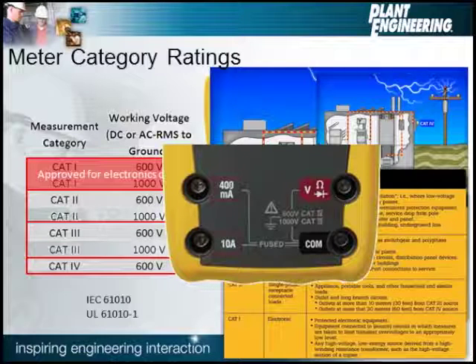Our Cat 2 meters are used for branch circuits, long branch circuits, and low incident energy exposures. Cat 3 is for service entrance, distribution panels, or high incident energy. And lastly, Cat 4 is for distribution, outdoor wiring, underground. If you want more detail on this, you can always look up the IEC or the Underwriters Laboratory standards for it, 61010. Now, as we can see on our meter here, it's rated for Cat 4 up to 600 volts and Cat 3 for 1,000 volts. So it has dual ratings.